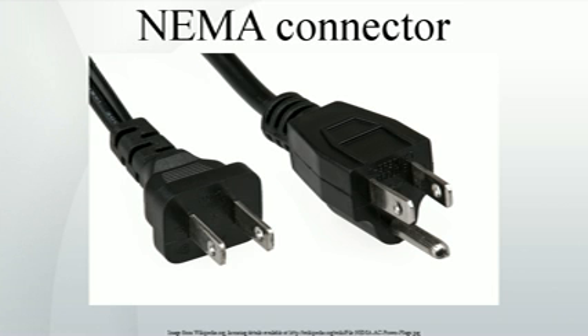NEMA 6 devices, while specified as 250V, may be used for either 208V or 240V circuits, generally depending on whether the building has a three-phase or split-phase power supply, respectively. The NEMA 6-20A or 6-30A found in many hotel rooms is often supplied with 208V and without a neutral.